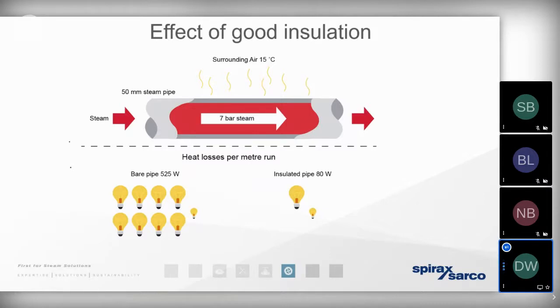It could well be that we've got an excess of erosion, corrosion, or water hammering in the distribution pipework. And maybe by increasing the grade of insulation that's present on the pipework, we can reduce the condensate burden and have a positive effect on each of those things.